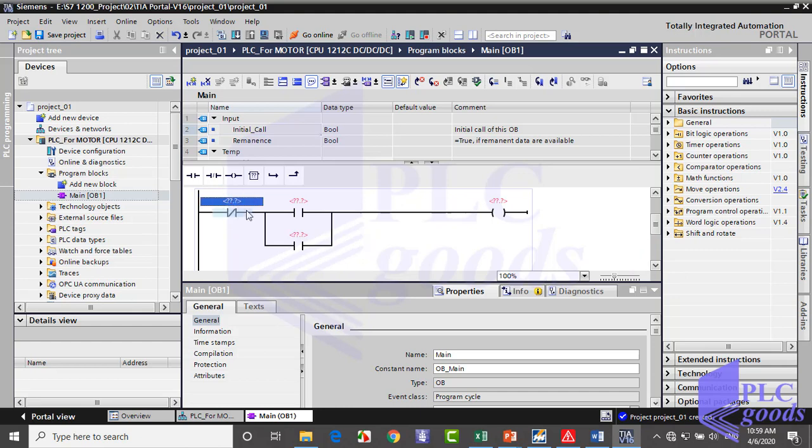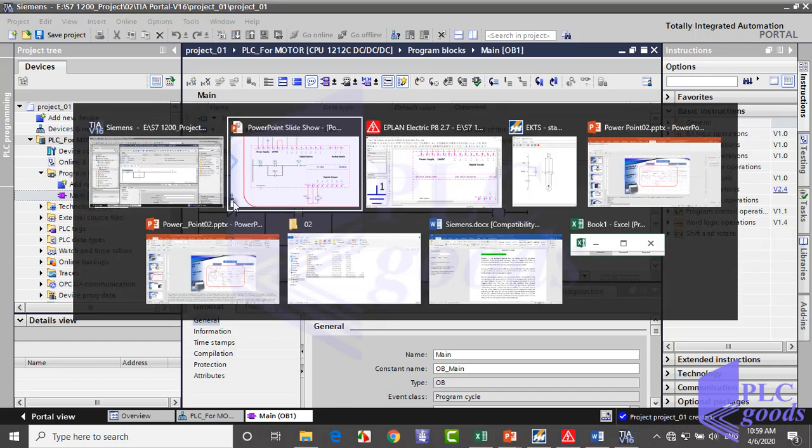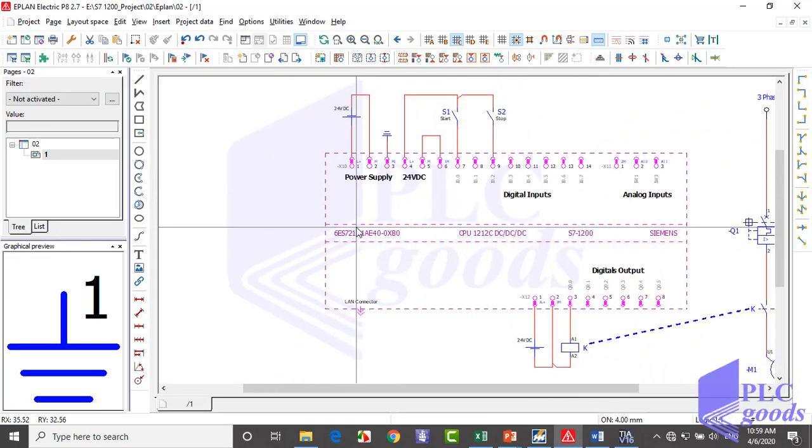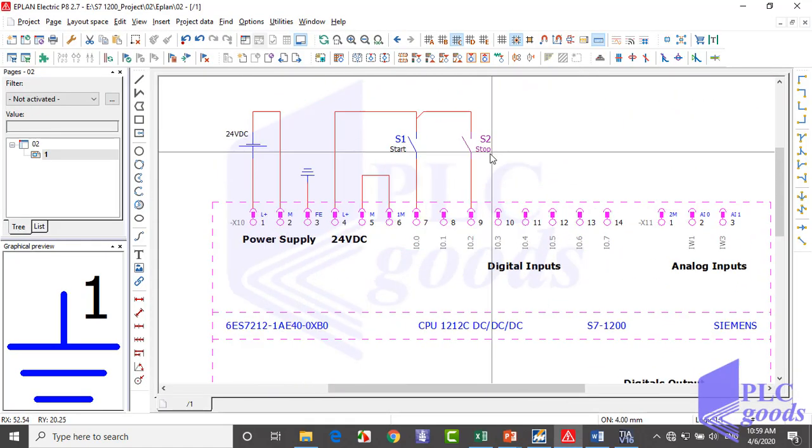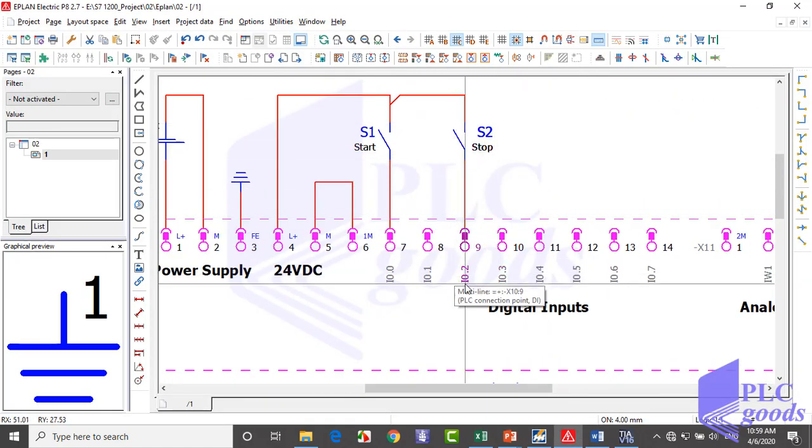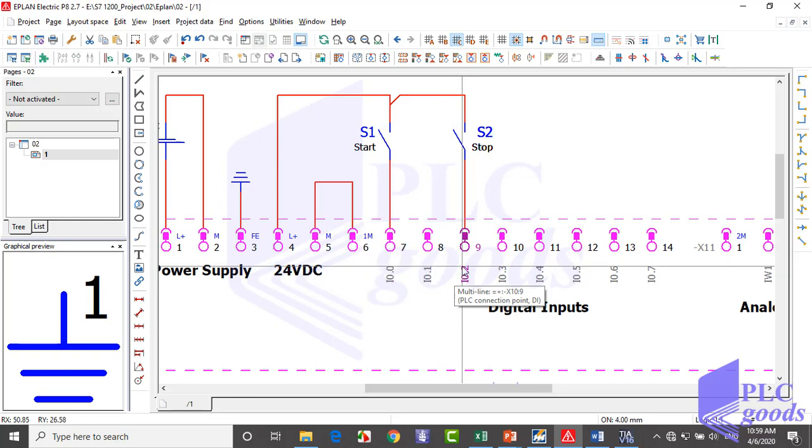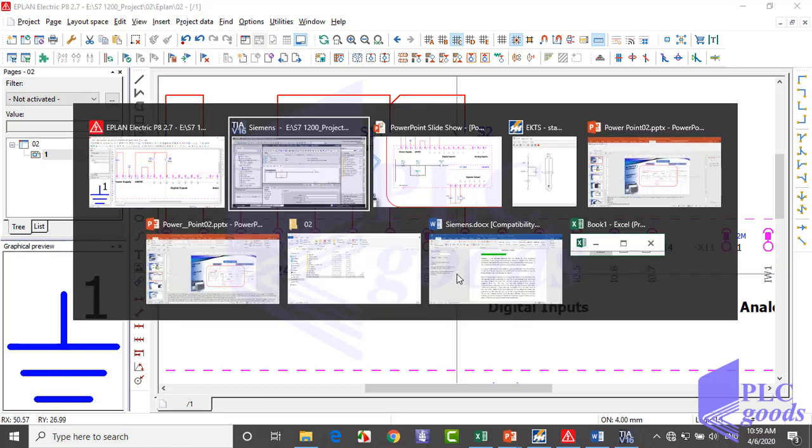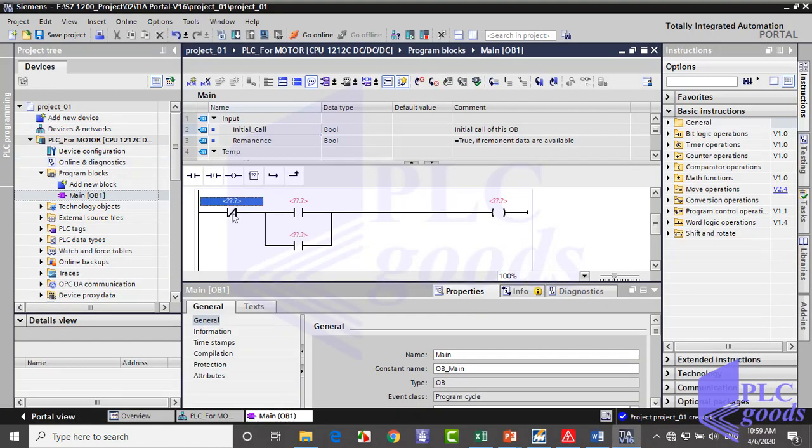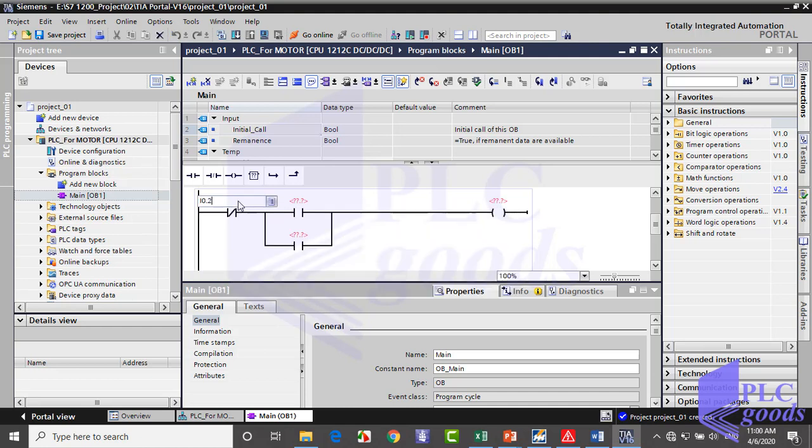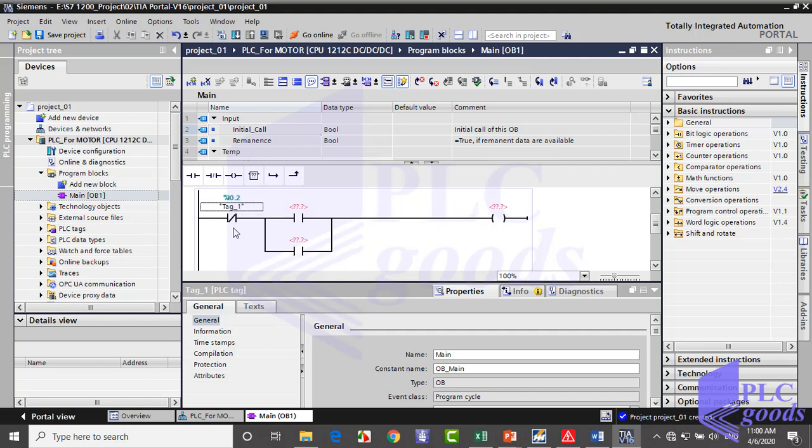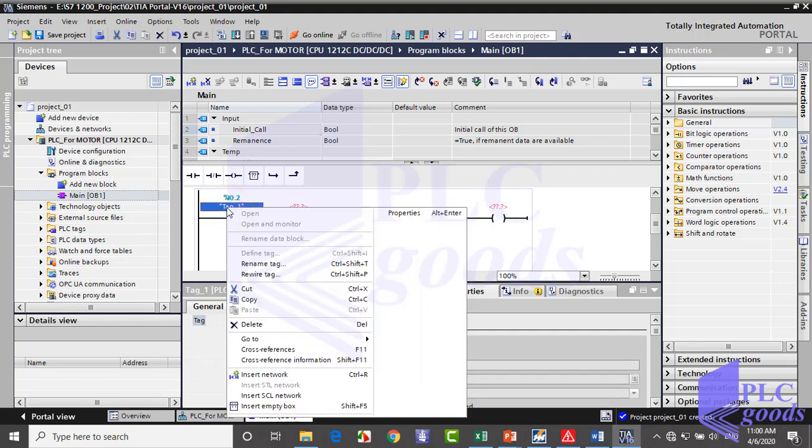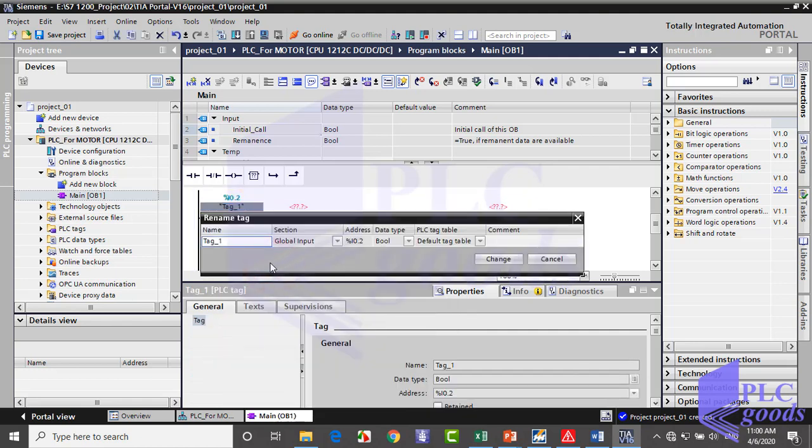Now, which address must we write here? Let me show the PLC wiring. The stop switch is connected to PLC input with this address I0.2. So I write I0.2 here. Then right-click and select rename tag. Here write a suitable tag for this address.